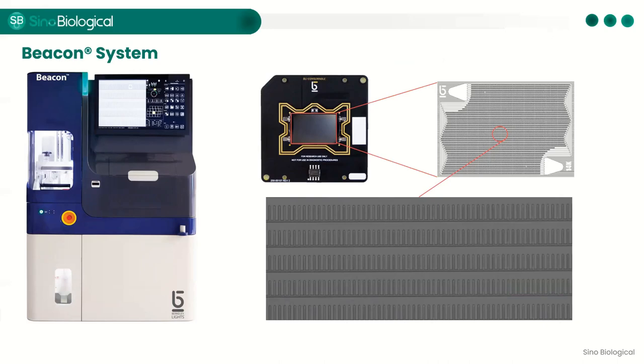Beacon is an automated device with functions of a cell incubator, biosafety cabinet, fluorescence microscope, and automated robotic arm, which integrates microfluidics, signal detection, and light-induced technologies. Based on morphology and fluorescence characterization of cells, the Beacon system can conduct cell isolation, cell culture, real-time detection of cell secretion, and multiplex detection directly on the chip. Target cells can also be exported through the Beacon system, which is highly automated and less dependent on operators. Let's take a look at the chip, which is the core component of the Beacon system.